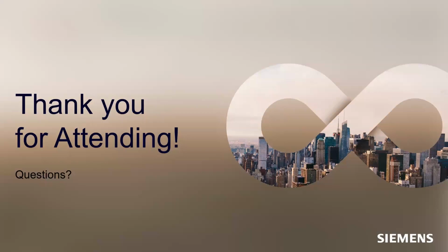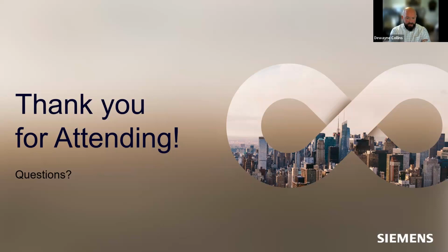How do you accomplish using technology to avoid statistical analysis on VAVs if the existing BAS doesn't have an automated VAV commissioning feature? There are a few ways to look at this. The analysis I showed is meant for assessment—it's meant to be directional. That doesn't mean you won't find value in additional engineering work, like statistical modeling, which is absolutely valid. But it behooves us to take a first pass and see directionally where we need to spend our time. If that initial check says these five pieces of equipment or four boxes are where we need to focus, that may include statistical analysis. But it's important to directionally understand where you're going before you spend that time.